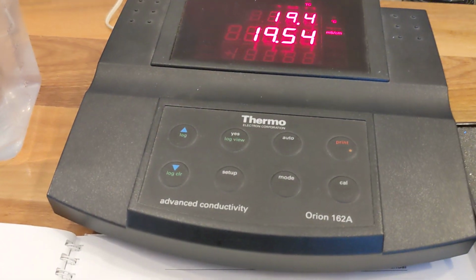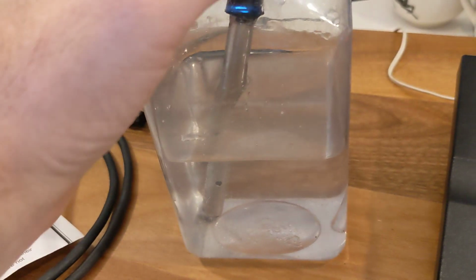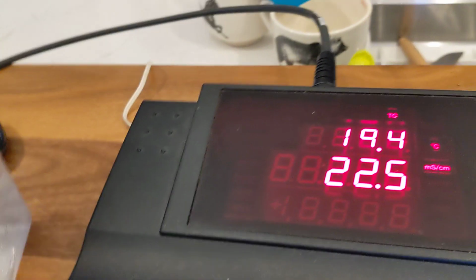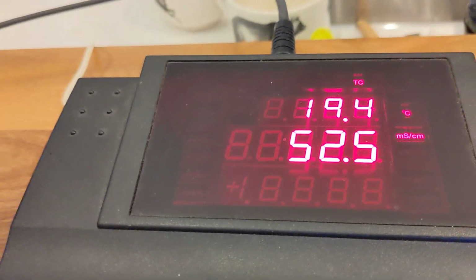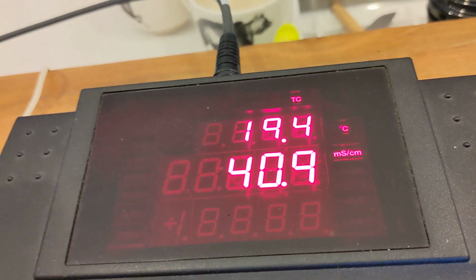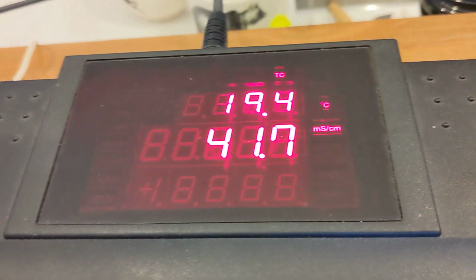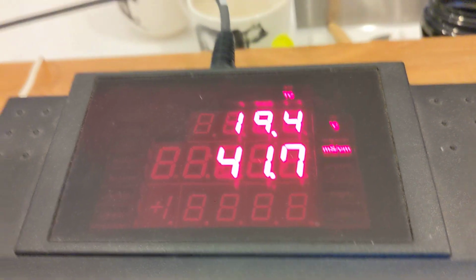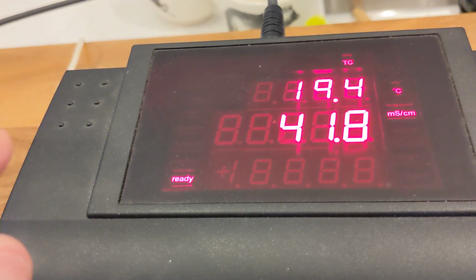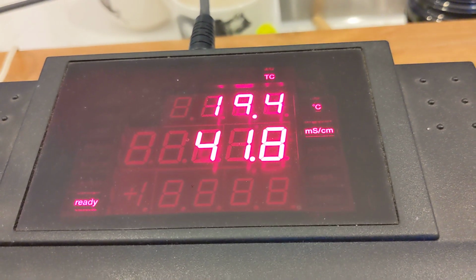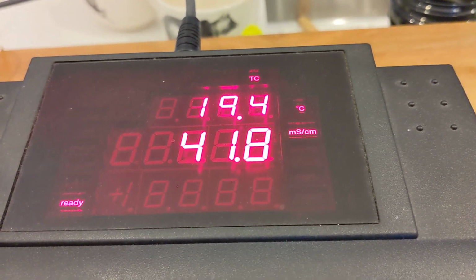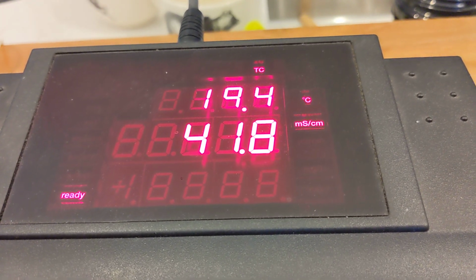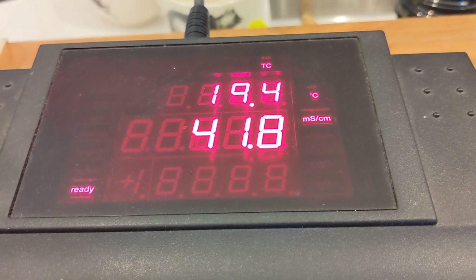We're making this water very conductive. It's raining. And it's 20 degrees C, so it's a little colder than standard. But this compensates. The TC up here says that there's a temperature sensor in the probe, and it compensates for the conductivity for the temperature of the solution. So 41 millisiemens at 19.4 degrees C. Not bad, not bad at all.